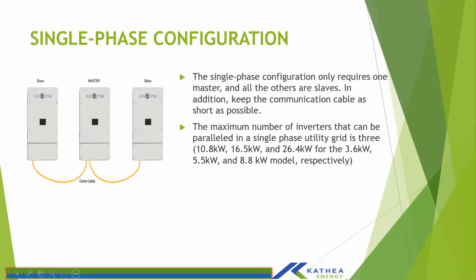It is recommended that you can connect up to 3 SunSynk inverters in parallel on a single phase. So with the 5.5, you can go up to 16.5 kilowatt, while with an 8.8 you can go up to 26 kilowatt on a single phase. With the single phase, you only have one master, and all other inverters will be slaves.